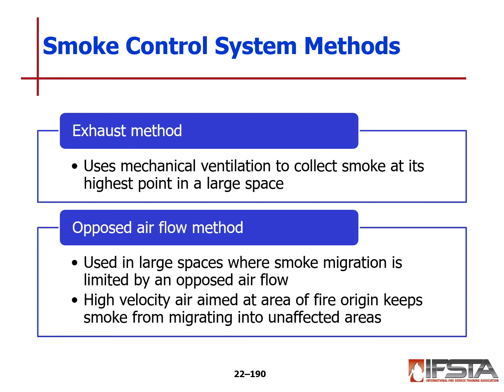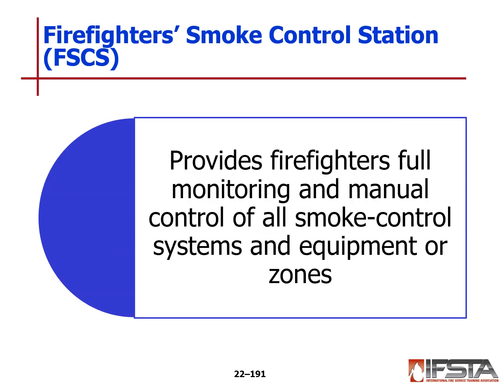The exhaust method uses mechanical ventilation to collect smoke at its highest point in the largest space. And an opposed airflow method is used in large spaces where smoke migration is limited by an opposed airflow. High velocity air aimed at an area of fire origin keeps smoke from migrating into the unaffected areas. Smoke control stations provide firefighters full monitoring and manual control of the system, the equipment and the zone. So that would allow us to pick and choose and control where we need it to be controlled and where not.